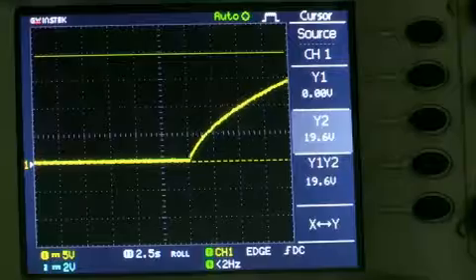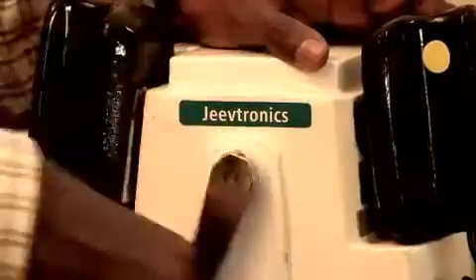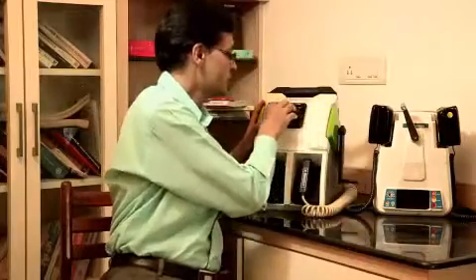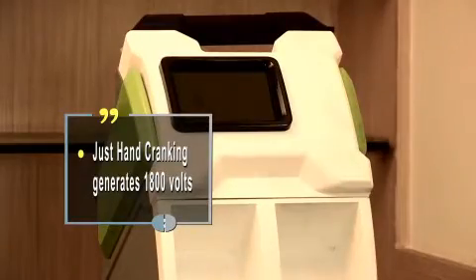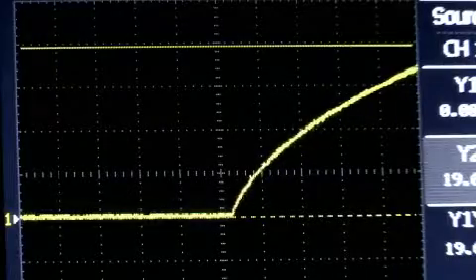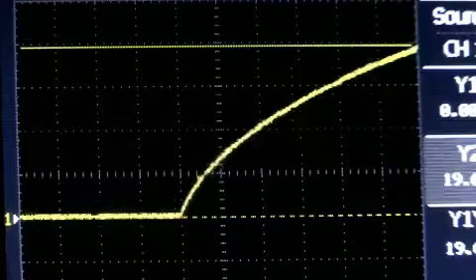They have together designed and developed a defibrillator which can be used in remote areas where there is no electricity, and is easily one-fourth the cost of routine defibrillators. As the user rotates the handle and cranks it for about 12 seconds, you can see the ECG of the patient in about five seconds. The device's ability to quickly generate 1800 volts necessary to defibrillate the heart in just 12 seconds by simply hand cranking is its foremost novelty.